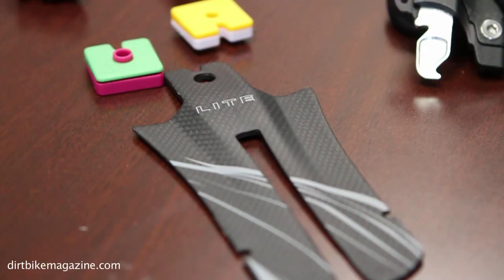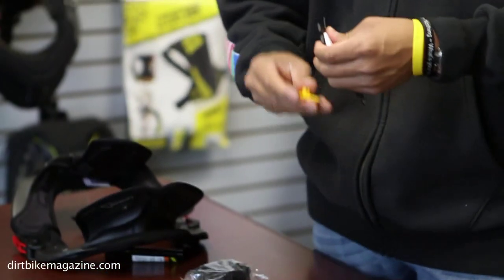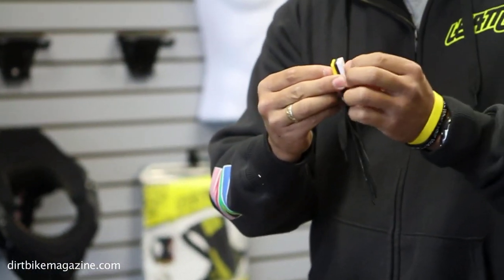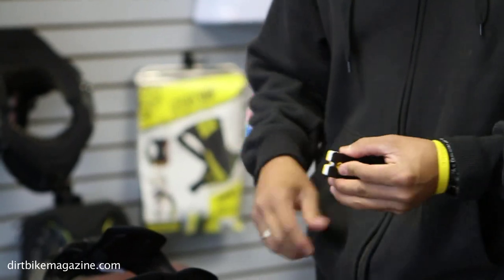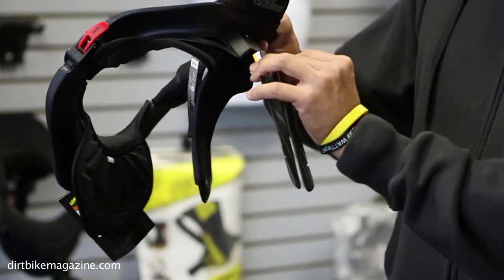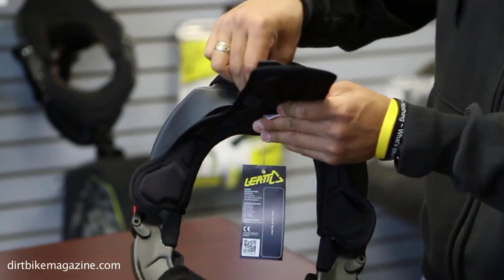You'll notice that we've got several different shims. These are used to take place here when you put the rear thoracic in. You can split these shims and change the angle of the brace. You achieve the different angles by placing the thoracic between the two. I'm going to go ahead and put it in the standard five degree position — the piece together with this piece on either side — and slide it up inside the brace. Once you get it in the brace, you can put this back in.